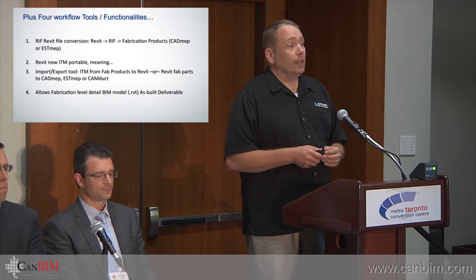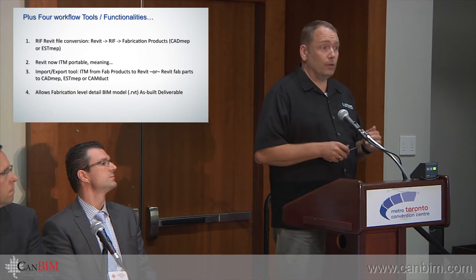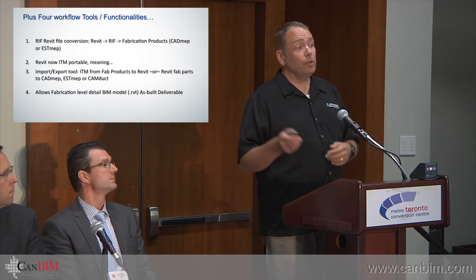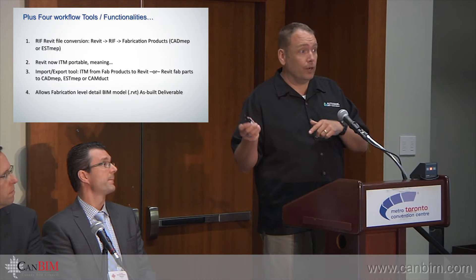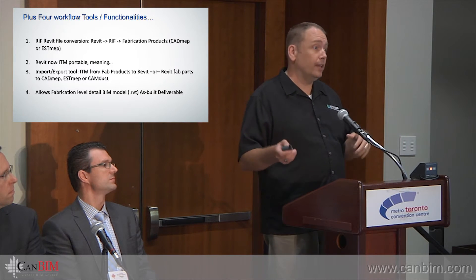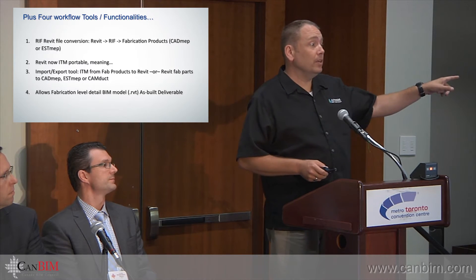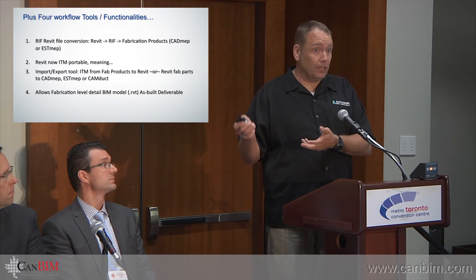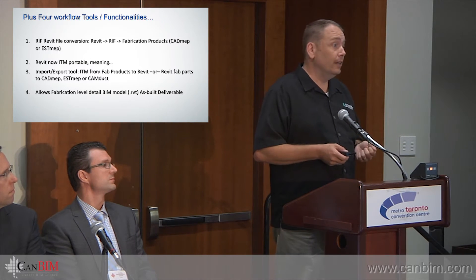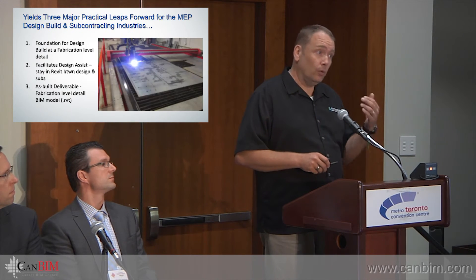Another key thing you can do with this technology is: if you're an MEP firm and you get your project to DD stage and want to make sure it's going to work, you can hand it off to a subcontractor who will review it for a fee. It used to be you'd take the Revit file, they'd convert it to CADMEP, make changes and augmentations, and hand back a CAD file you'd have to get back into Revit. Not anymore. Because Revit now reads ITM content, you give them the Revit file, they make whatever changes they want with fabrication-level detail content, and hand you back a hybrid Revit file. It's changing the workflows and meeting the demand of owners who want a fabrication-level detail Revit file.